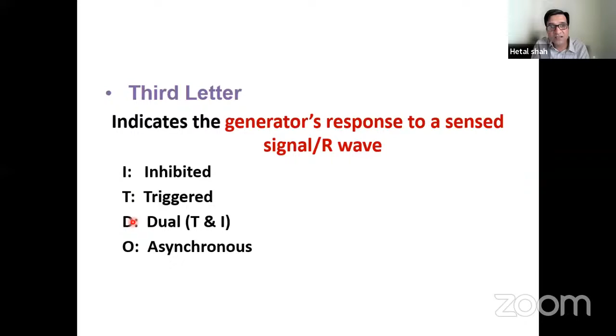In the same way, the ventricle is being paced, there is no chamber being sensed, and it is asynchronous. Let's say VVI, which is very common. The ventricle is being paced, the ventricle is being sensed, and if there is any ventricular activity, it will give inhibition, so the machine will not pace. So let's say this patient is VVI. The ventricle is the chamber which is going to be paced, but the sensing will come from the ventricle. If there is any of the patient's own ventricular activity, the machine will sense that and inhibit, so the machine will not give anything. So there will be a non-competitive kind of pacing.